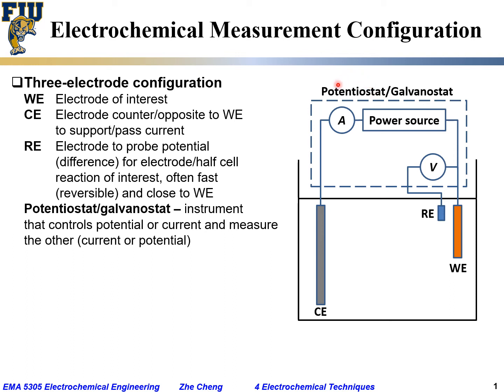It is a complex instrument that controls potential or current and measures the other. For a potentiostat — 'stat' means constant — you control constant potential and measure current. For a galvanostat — 'galvano' is for current — you maintain constant current and measure the change in potential. Quite often it is a single instrument that can control either constant potential or constant current.